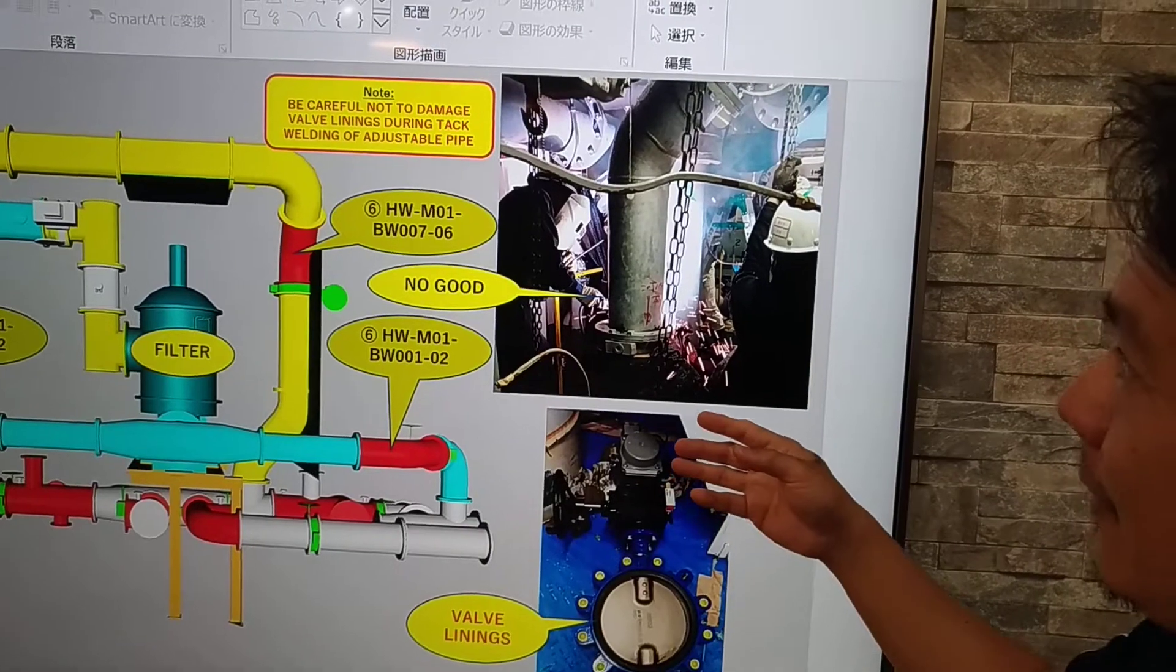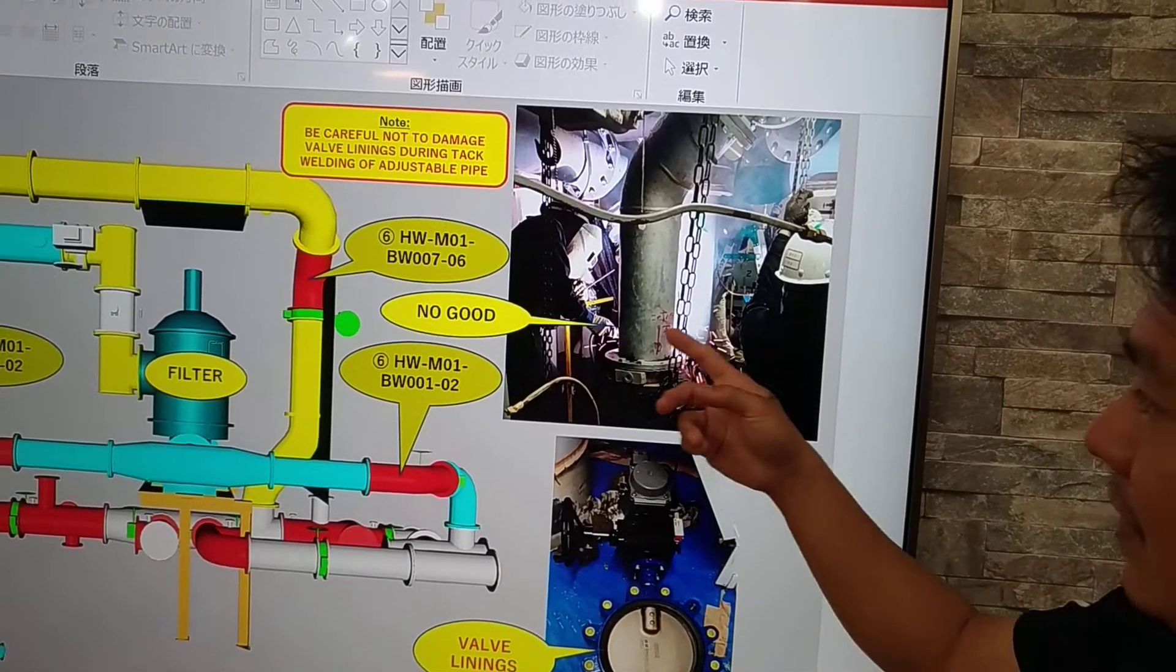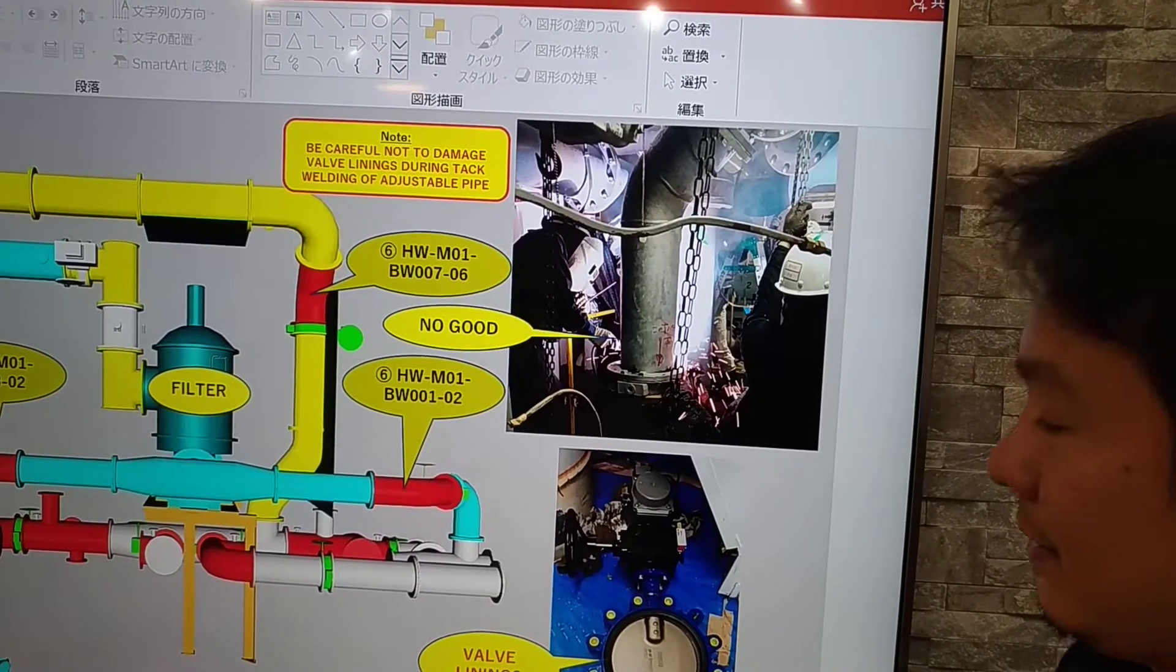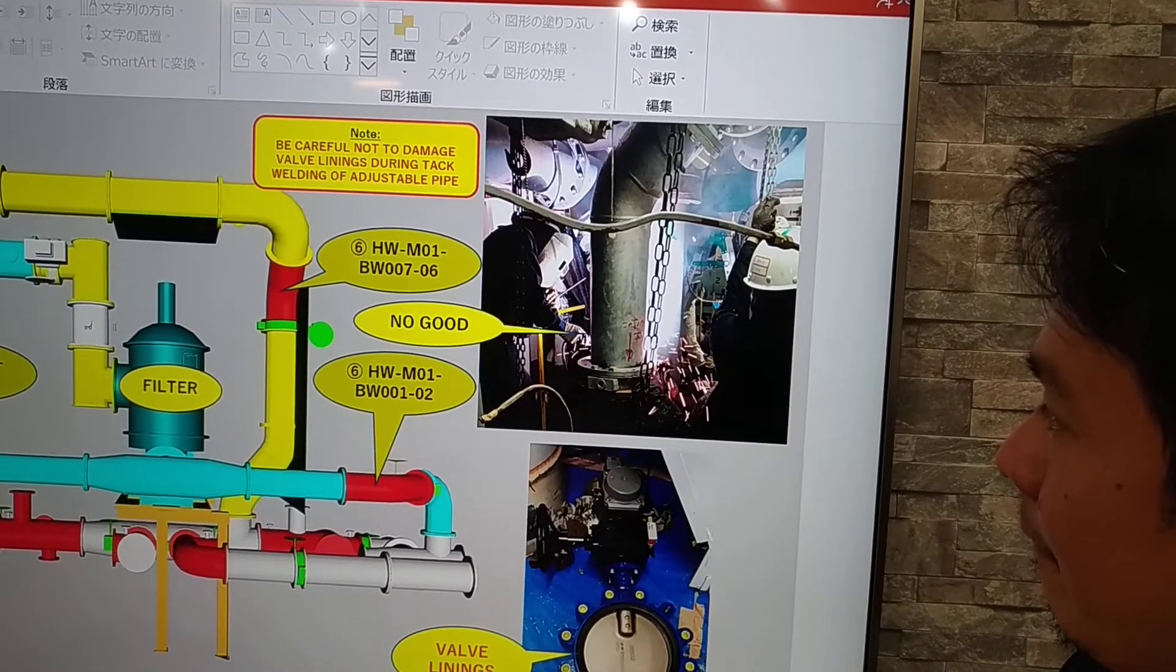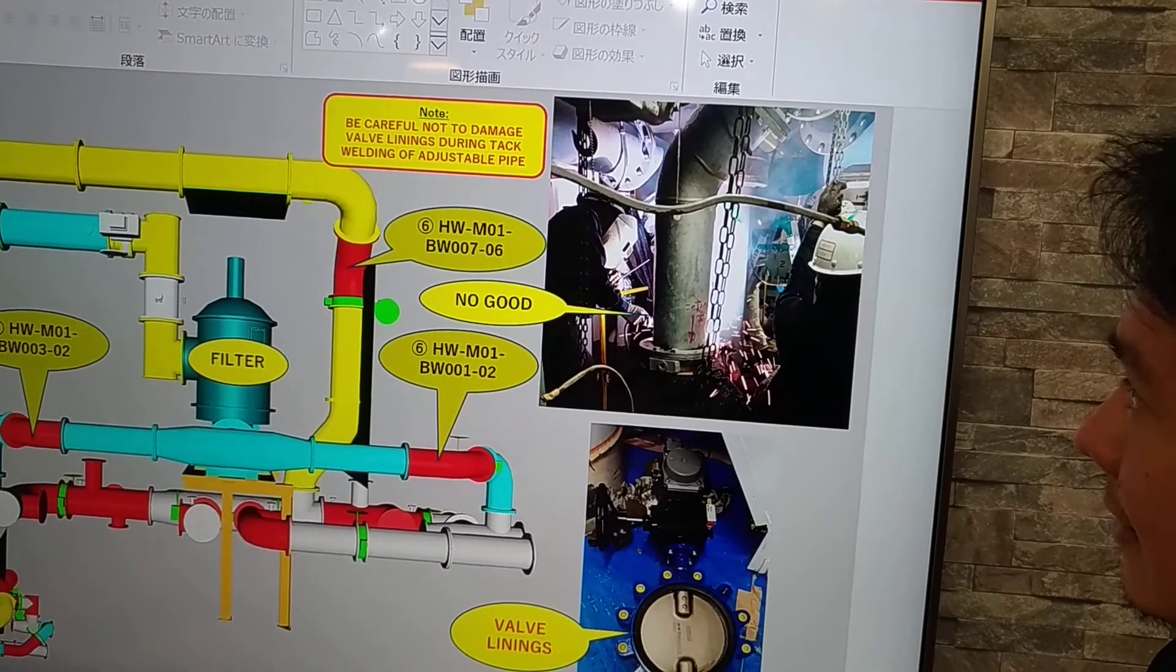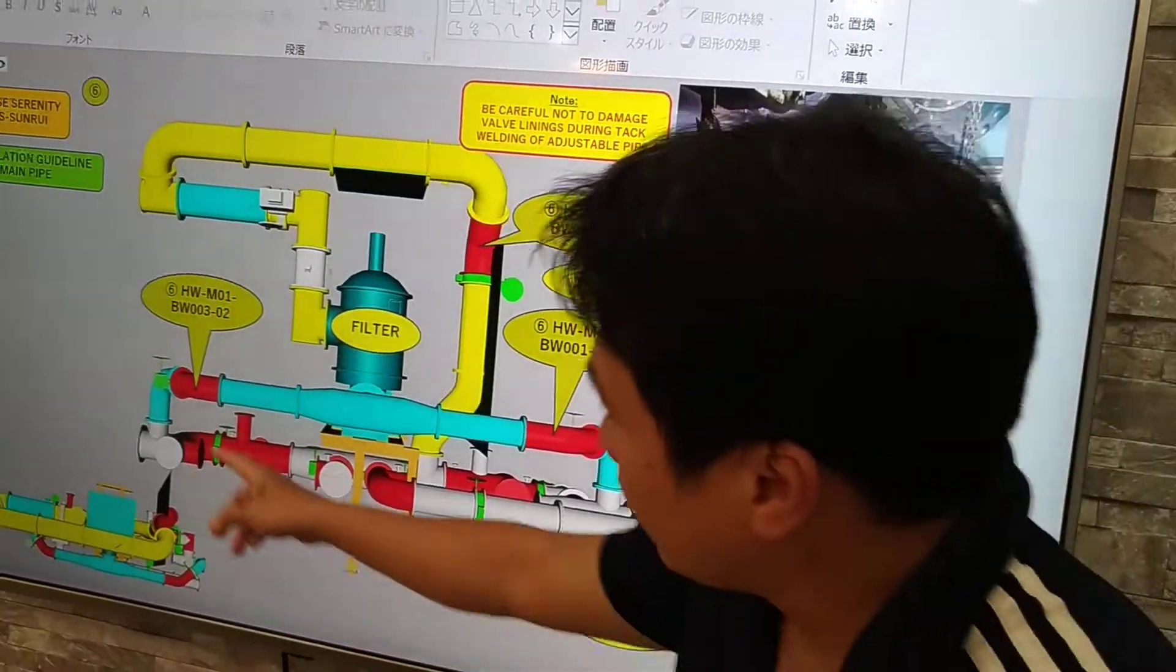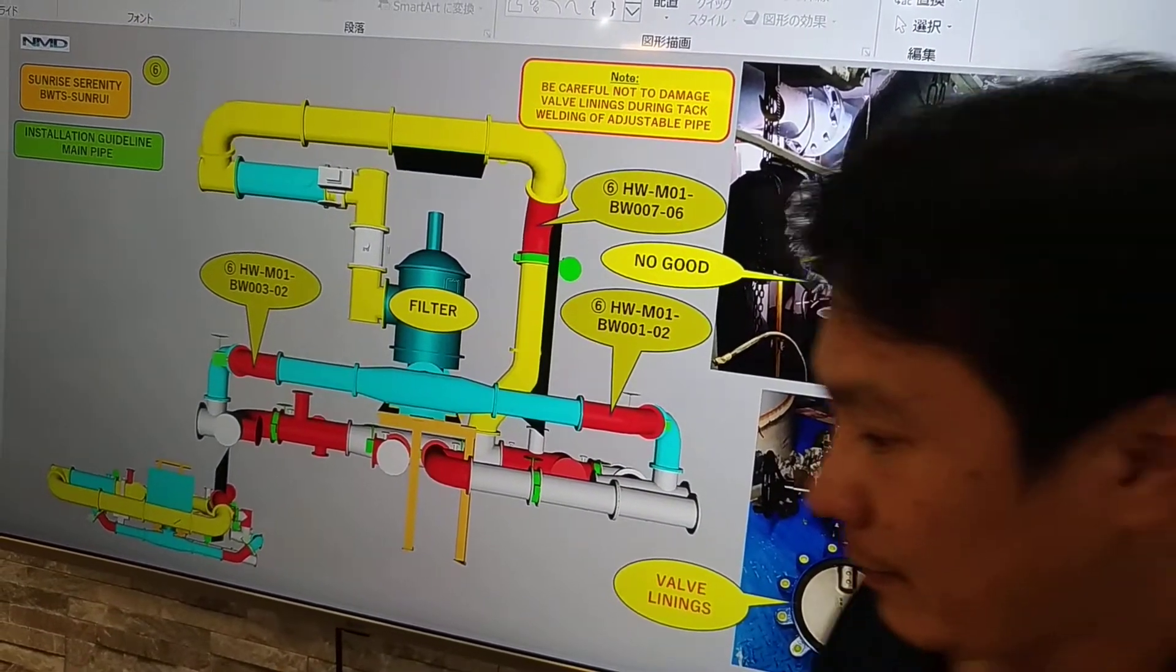Be careful not to damage the valve linings. Because as we know, welding is almost 1000 degrees. So just have only tack welding. Always be careful with the valve linings. So we have here three valves. So be careful during tack welding.